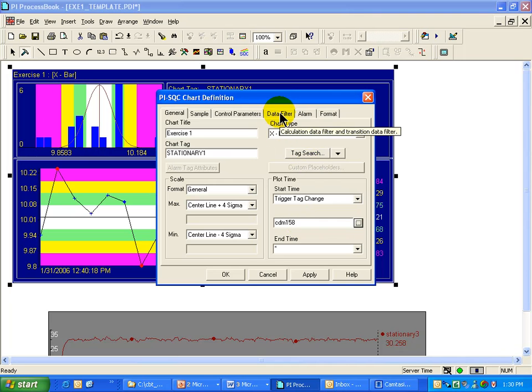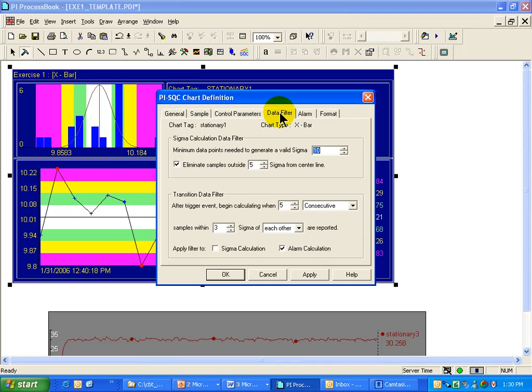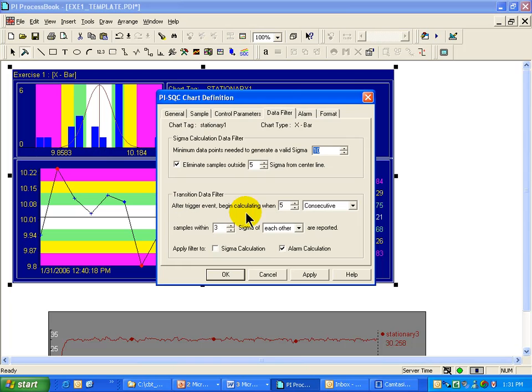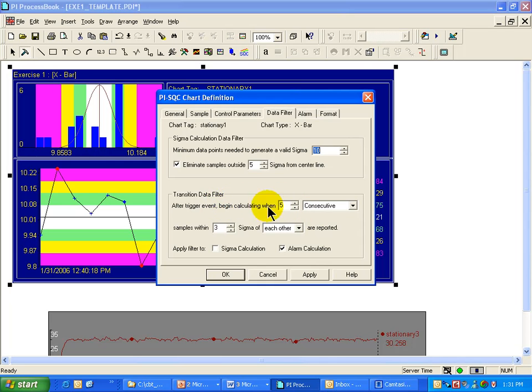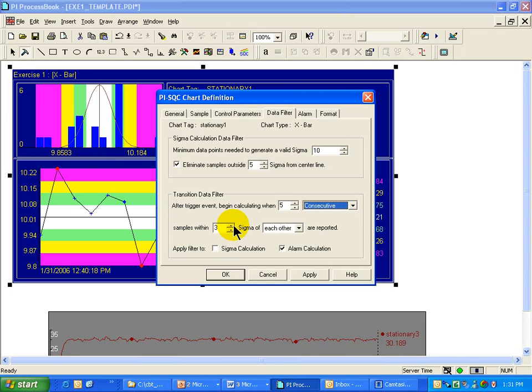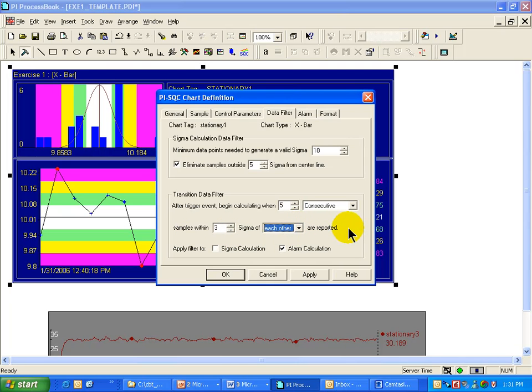When that happens, as you transition, we would like to be able to ignore some things. During any kind of product change, usually there's some kind of transitional period where SQC alarms can really just do more harm than good. They're just going to produce nuisance results. What we're suggesting is with those trigger tags, you can specify how many consecutive or non-consecutive values need to appear within a certain number of sigma of either each other or of the center line before we start to resume calculation.